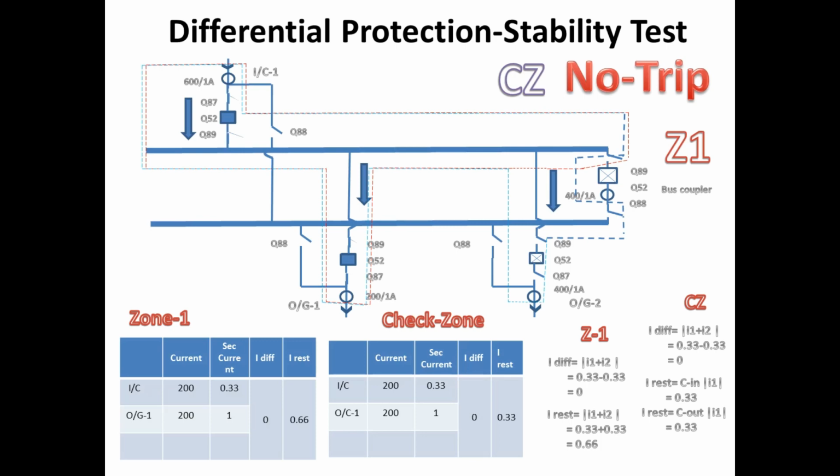Now there is no differential current for zone 1 and check zone, so there will not be a trip over here. Now we can go for checking the transfer bus.